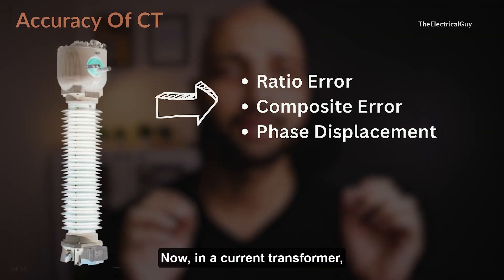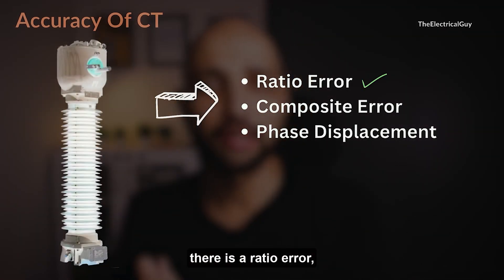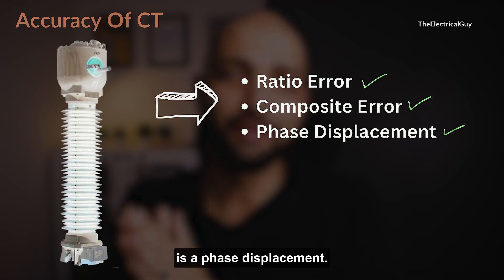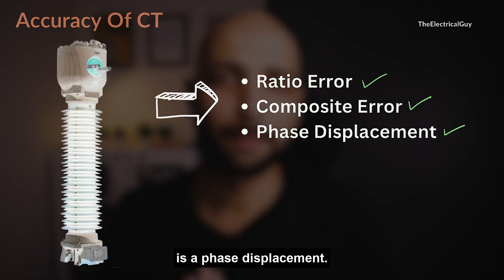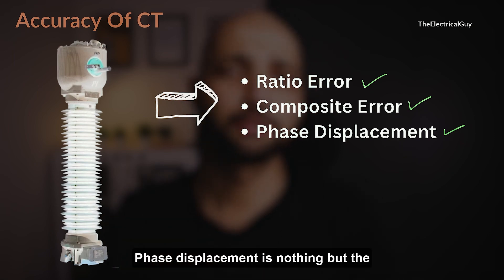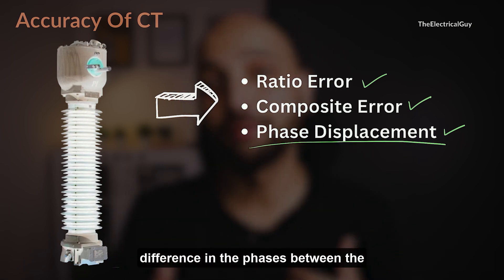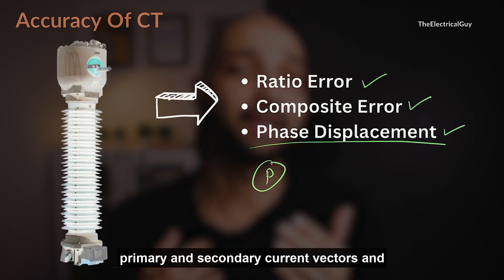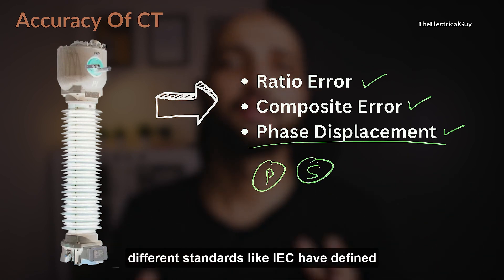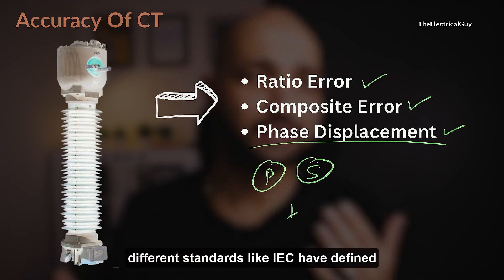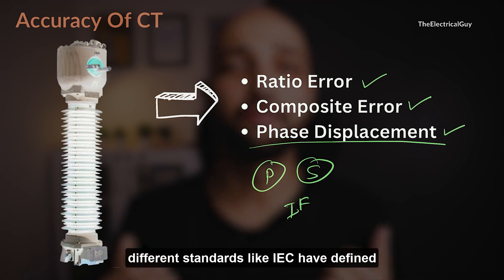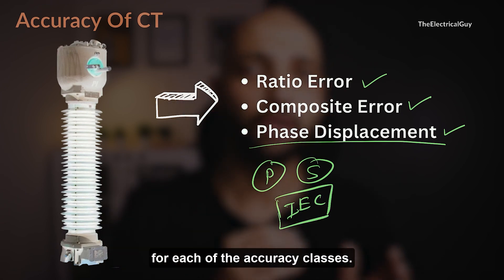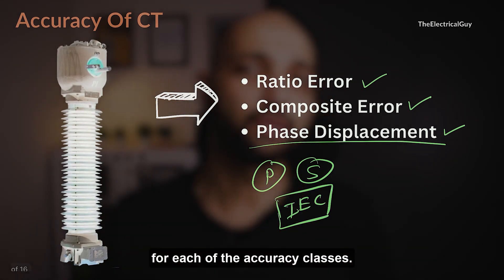In a current transformer, there is a ratio error, a composite error, and a phase displacement. Phase displacement is the difference in phases between the primary and secondary current vectors. Different standards like IEC have defined certain limits for each of these errors for each of the accuracy classes.